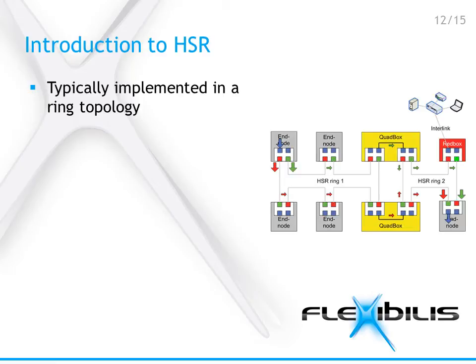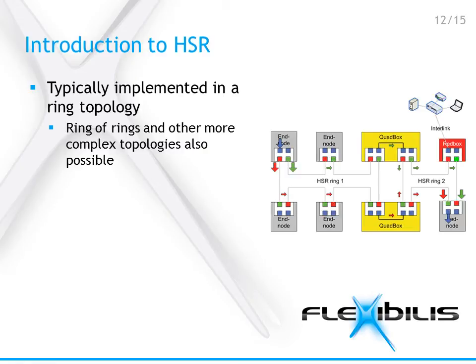HSR is typically implemented in a ring topology. While a ring is the most common at the moment, it is not the only possible way — HSR can also be constructed as a ring of rings and other more complex topologies. Ring topology doesn't require separate switches, since the nodes themselves do the switching, as every node has an internal Ethernet switch.